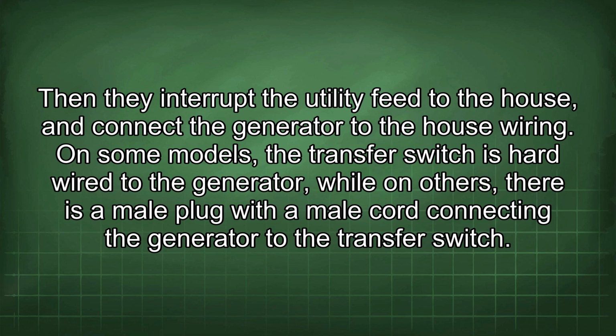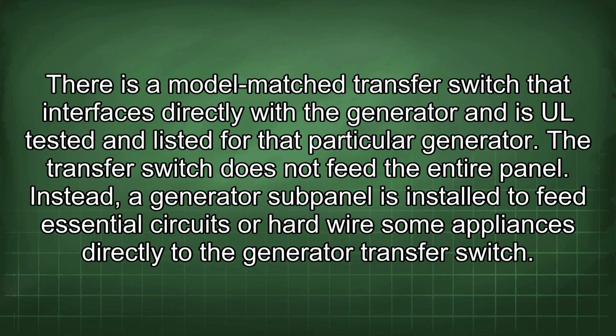On some models, the transfer switch is hardwired to the generator, while on others, there is a male plug with a male cord connecting the generator to the transfer switch. There is a model-matched transfer switch that interfaces directly with the generator and is UL tested and listed for that particular generator. The transfer switch does not feed the entire panel.